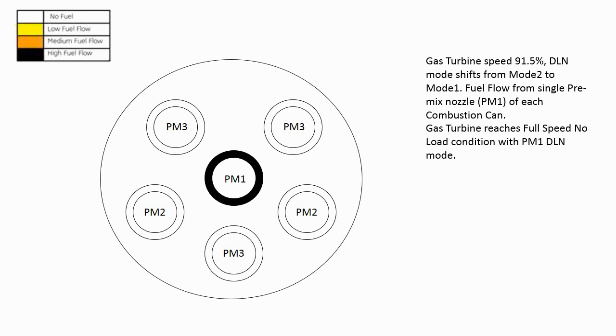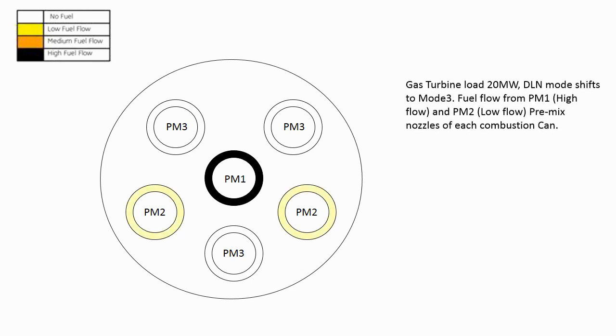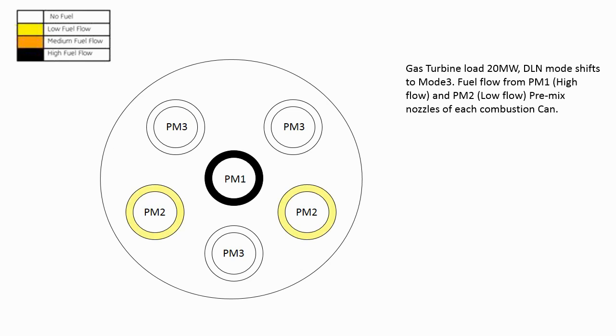Gas turbine reaches full speed no load with PM1 DLN mode. When 7FA gas turbine load reaches 20 megawatt, DLN mode shifts from mode 1 to mode 3. Fuel flows from PM1 and PM2 of each combustion can. Note that more fuel flows from PM1 while from PM2 fuel flow is low.